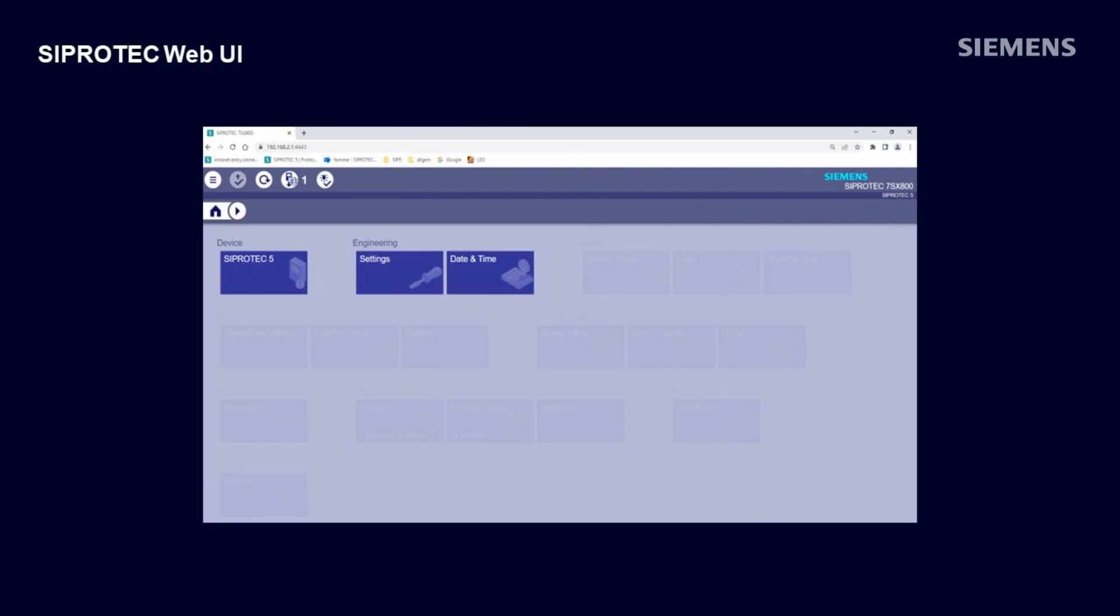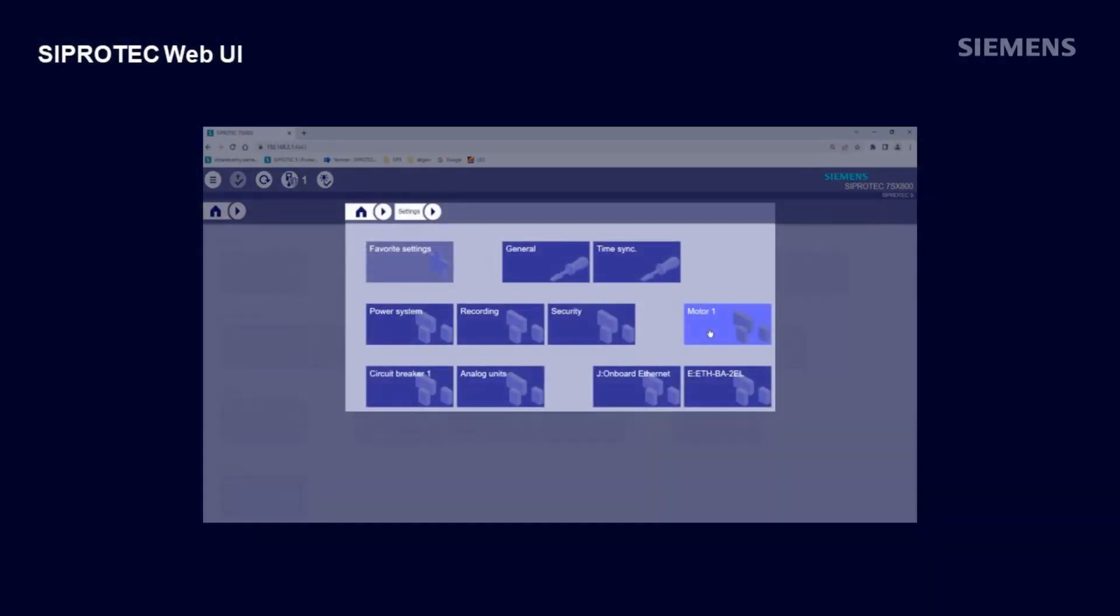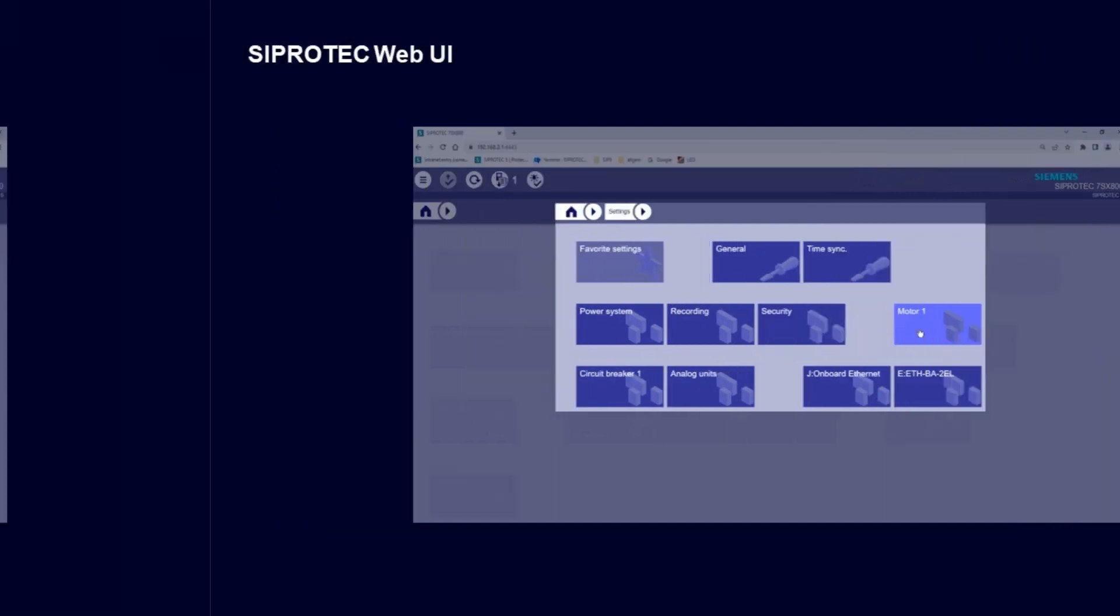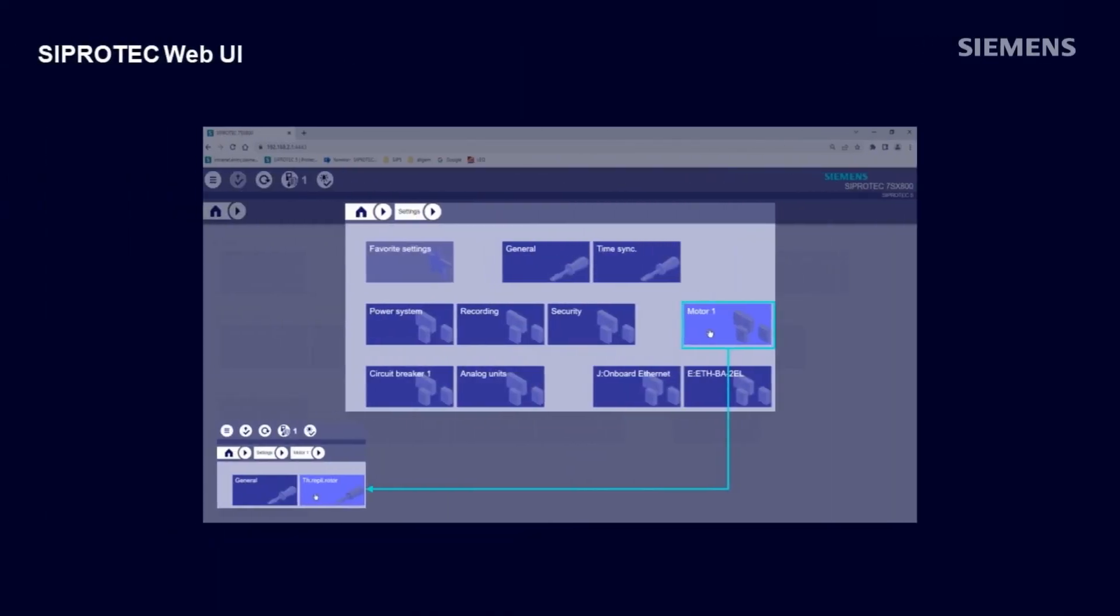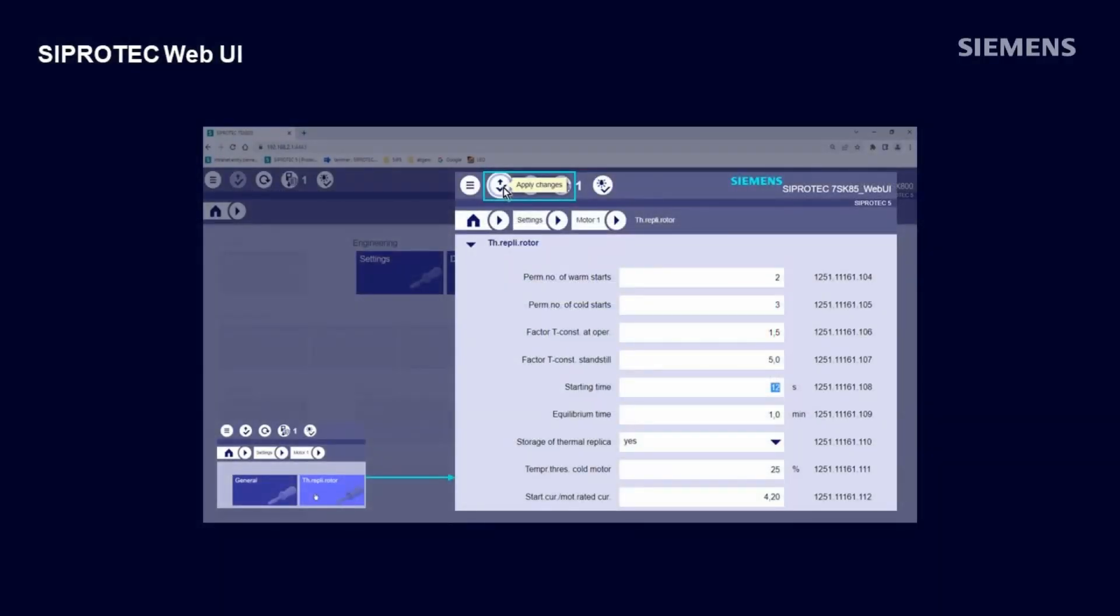Clicking on the settings tile in the engineering group, we get an overview on the function group level. When we select, for example, the motor 1FG, we reach the next lower level with all the functions that belong to this FG. Clicking, for example, on the tile of the thermal replica rotor function, all the settings are opened. Now we can modify settings in this function and if necessary navigate also upwards and downwards into other functions. At the end, if all setting changes are done, we click on the apply changes button in the top icon list, and settings are downloaded into the connected protection device.